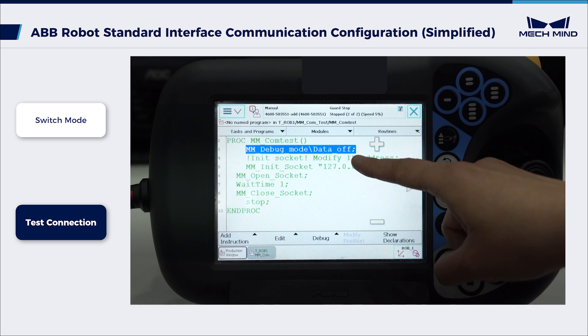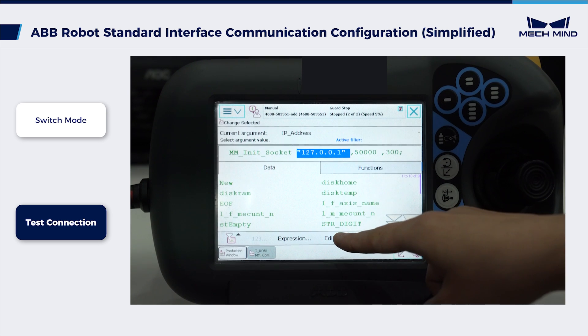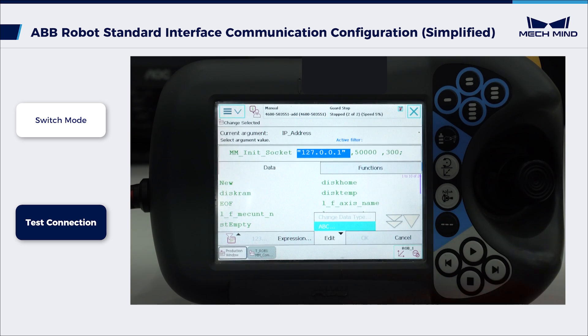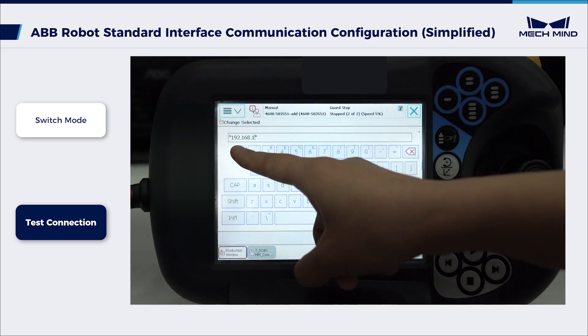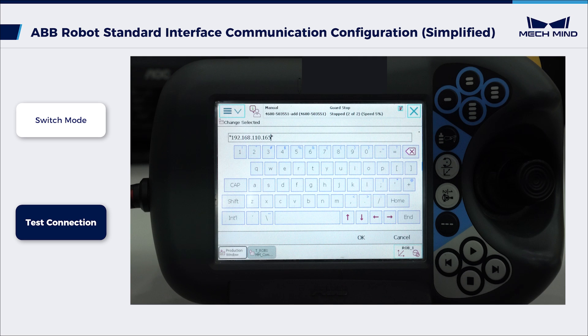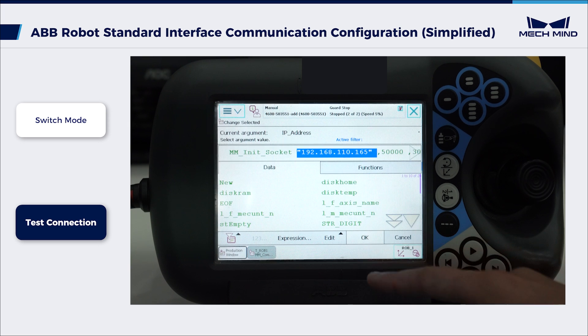Double-tap the IP address. Select Edit, then choose ABC. Change the IP address to the IP address of the IPC. If the host port number set in MechVision is modified, the port number 50,000 here should be changed to the host port number in MechVision. Click OK, then click OK again.